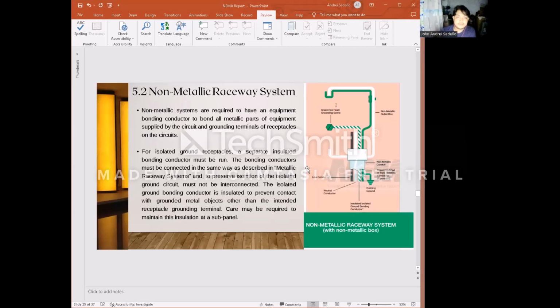Next is the non-metallic raceway system. Non-metallic systems are required to have an equipment bonding conductor to bond all metallic parts of equipment supplied by the circuit and the ground terminal of receptacles on the circuits. For isolated ground receptacles, a separate insulated bond conductor must be run. The bonding conductors must be connected in the same way as described in the metallic raceway system, and to preserve isolation, the isolated ground circuit must not be interconnected. The isolated ground bonding conductor is insulated to prevent contact with grounded metal objects other than the intended receptacle ground terminal. Care may be required to maintain this insulation to a sub-panel.